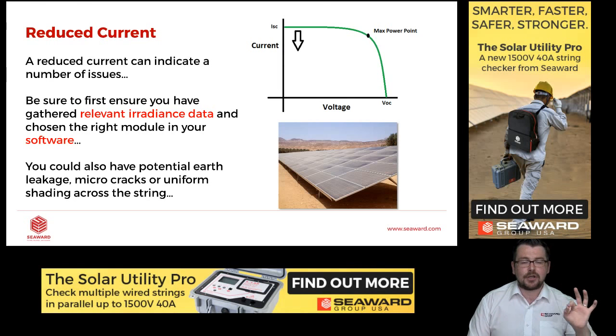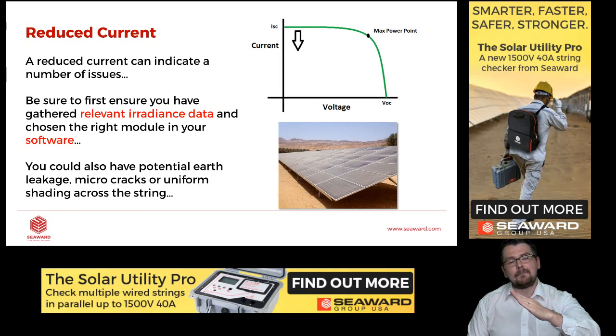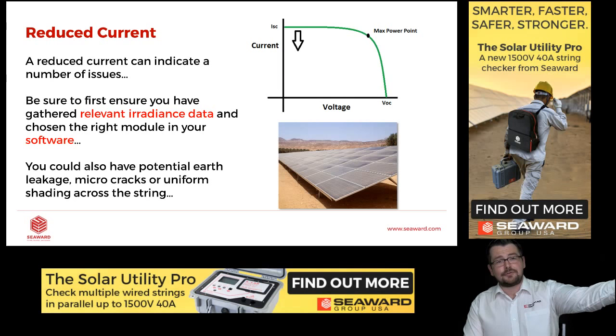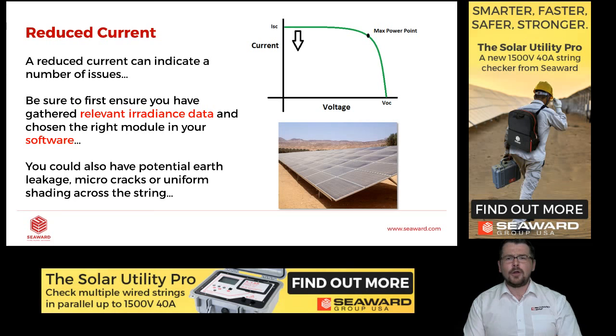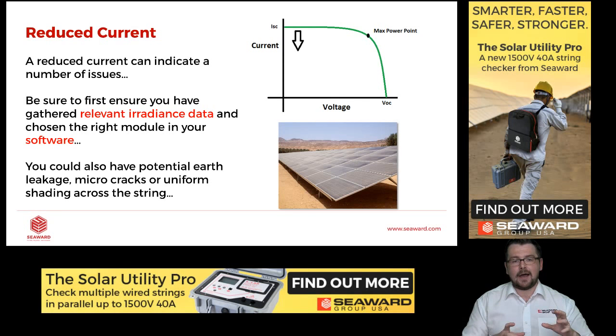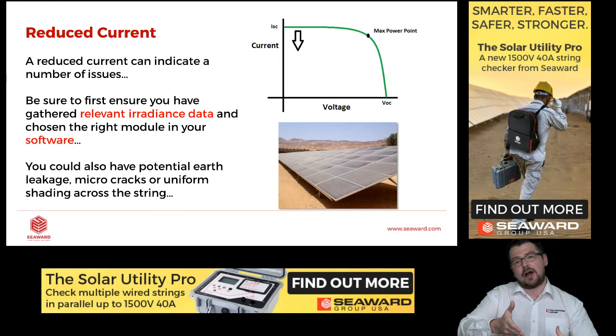So this goes back to us that we should have the irradiance meter in the same plane, in the same azimuth as the PV array. But potentially, we could also have earth leakage, micro cracks, or uniform shading. And if you haven't done your visual inspection and you test a string that is 200-300 feet down the way, you might not know that it's covered in dirt. And you think, oh, I have low current on my IV curve. Yes, because you didn't take a look and you didn't clean the panels. So this is vital. And also with micro cracks, as I mentioned earlier, this could be a path of increased resistance through the cell. You might want to just pull out your IR camera and take a look and see if you find any hot spots.